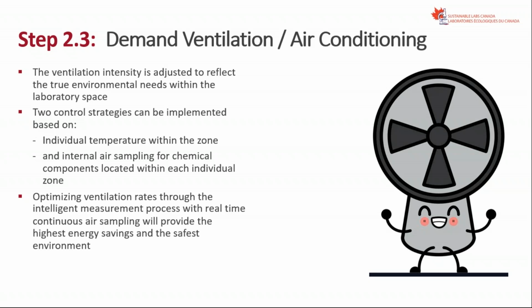The second option, which is important to bring up here, and which would work very well, is when internal air sampling is provided to verify the amount of chemical components in the airstream of each specific area. Based on that, the amount of air can be delivered more or less, providing a dilution capability and increased exhaust capability from the laboratory space. Now, the chemical compound can be a VOC compound, or it can be a particle counter attached to this system.